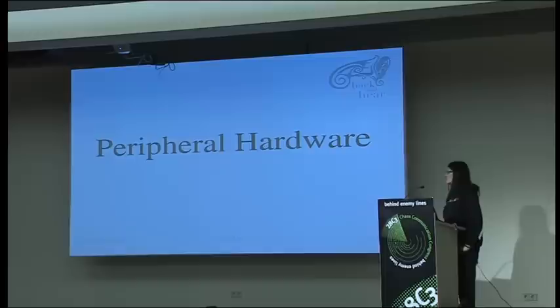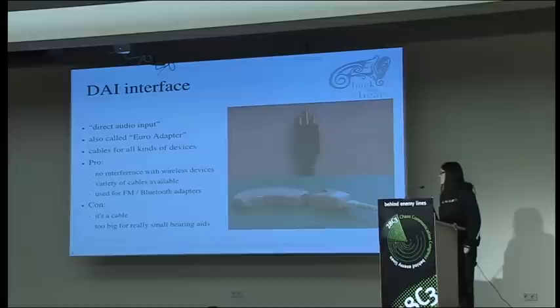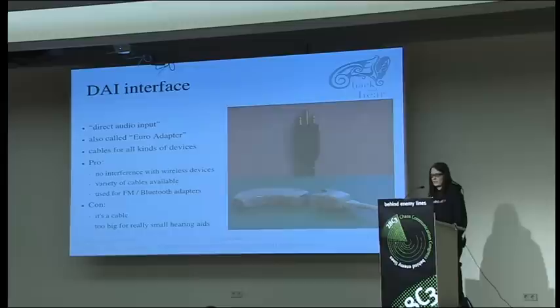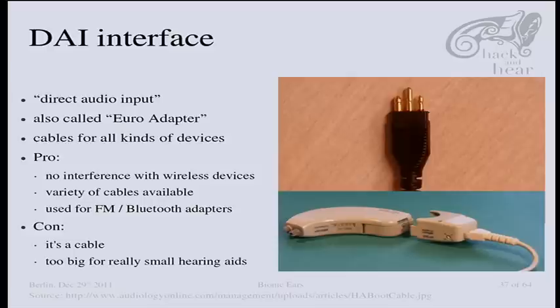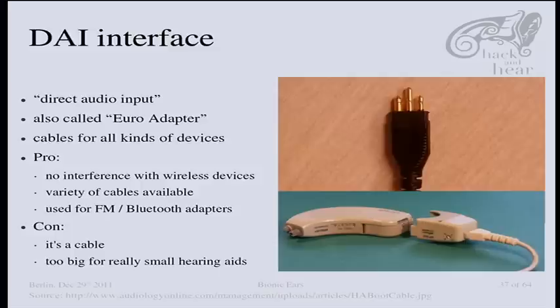There is some peripheral hardware I'd like to present. There are different interfaces you can use to plug into your hearing aids. The oldest one is the direct audio input, which is just a cable that connects to the hearing aids with a shoe-like connector. It has the pros and cons of cables — you feel like being on a leash, but you also have no interference with wireless devices. It's usually used to plug in FM or Bluetooth adapters. It's pretty old technology but still around, although for really small hearing aids the plug is too big so they leave it out.